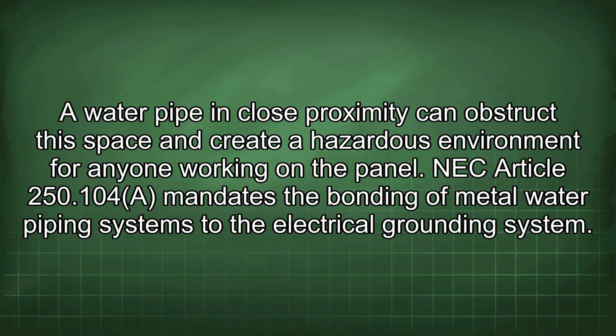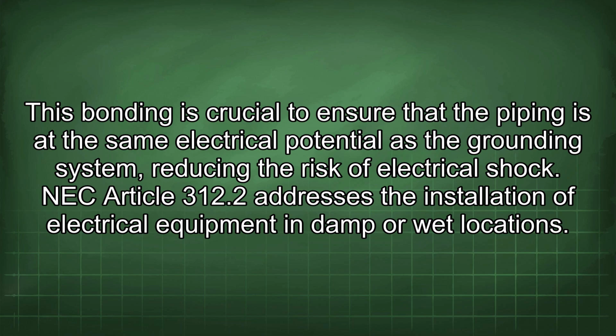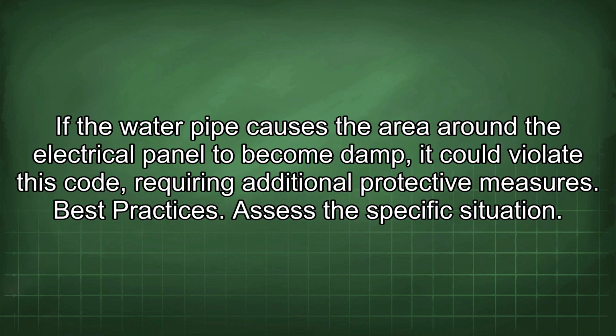NEC Article 250.104 mandates the bonding of metal water piping systems to the electrical grounding system. This bonding is crucial to ensure that the piping is at the same electrical potential as the grounding system, reducing the risk of electrical shock. NEC Article 312.2 addresses the installation of electrical equipment in damp or wet locations. If the water pipe causes the area around the electrical panel to become damp, it could violate this code, requiring additional protective measures.